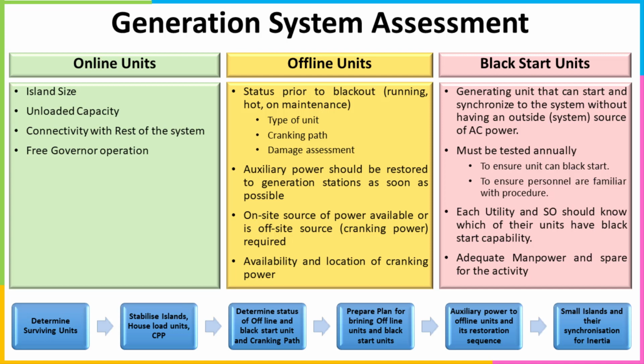In those power plants, you can have some auxiliary in terms of a battery, or in terms of a generator, a small DG set already there to provide the auxiliary supply to bring back the unit immediately. So they have their own auxiliary supply arrangement at the local level, and you can bring the unit quite fast. Based on that, you start providing the cranking power, start making a smaller island and restore the loads. You try to go to the nearby critical loads, and to the nearby thermal station, which can be revived immediately. Based on that, you charge lines and provide the supply to the nearby substations.